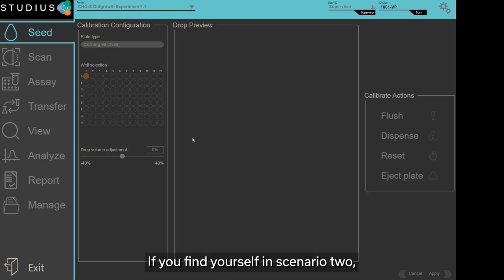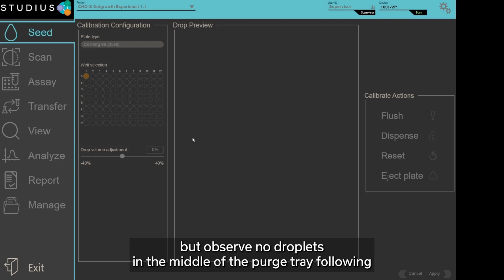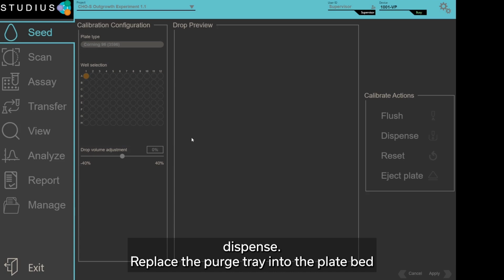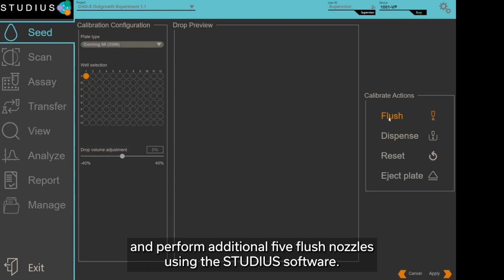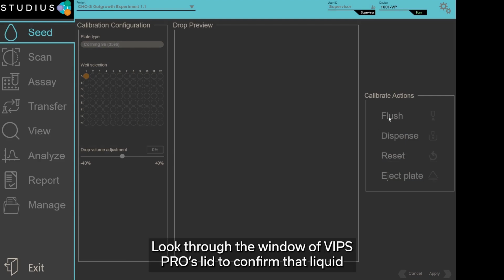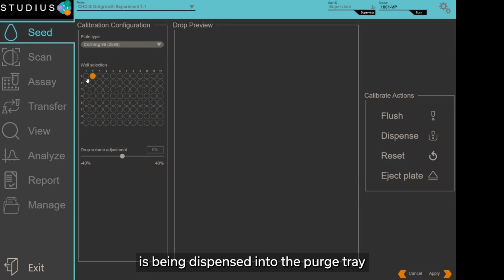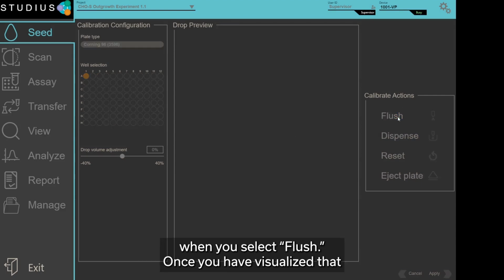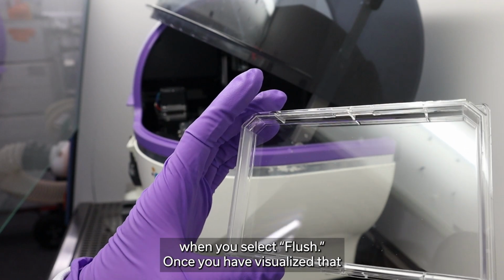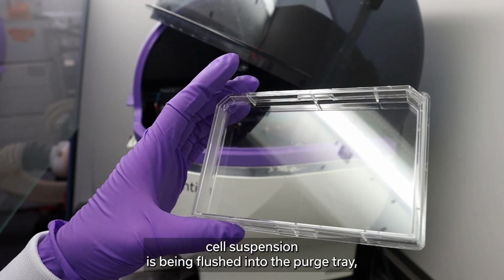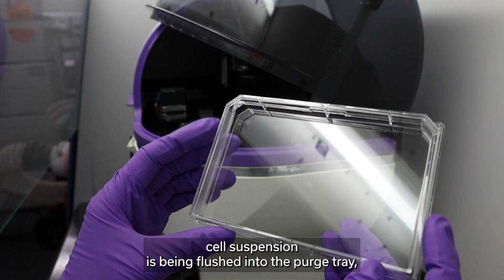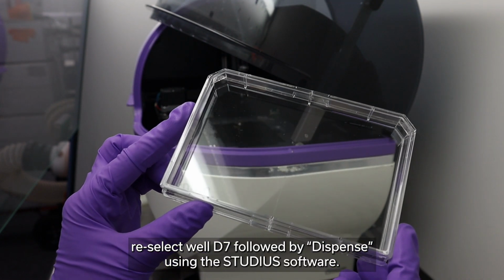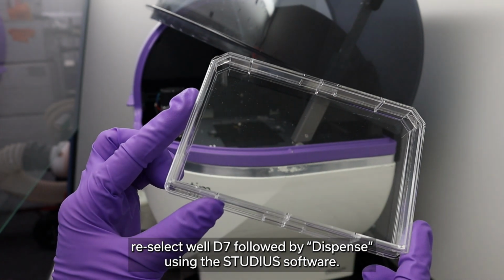If you find yourself in scenario 2 but observe no droplets in the middle of the purge tray following Dispense, replace the purge tray into the plate bed and perform additional 5 flush nozzles using the STUDIUS software. Look through the window of VIPS Pro's lid to confirm that liquid is being dispensed into the purge tray when you select Flush. Once you have visualized that cell suspension is being flushed into the purge tray, reselect well D7 followed by Dispense using the STUDIUS software.